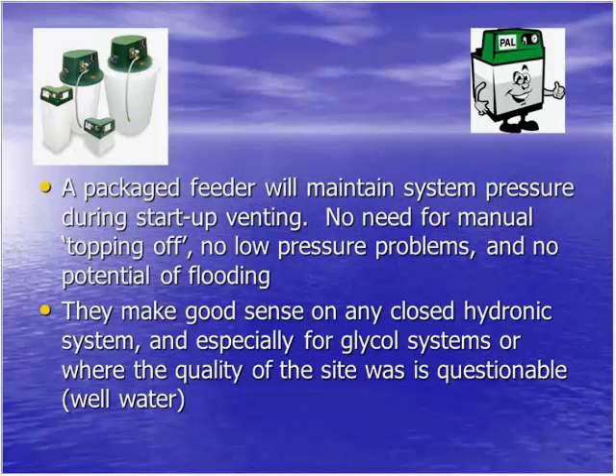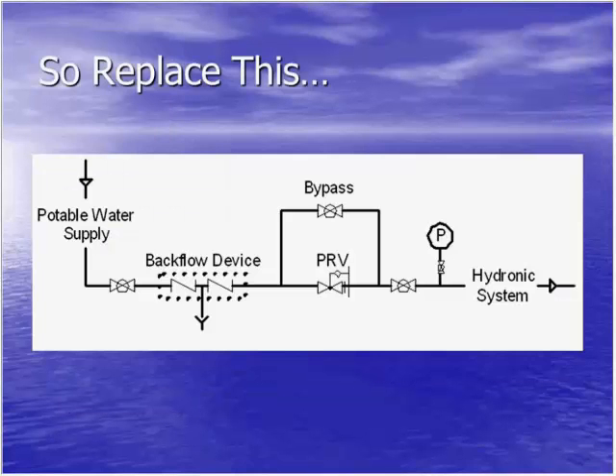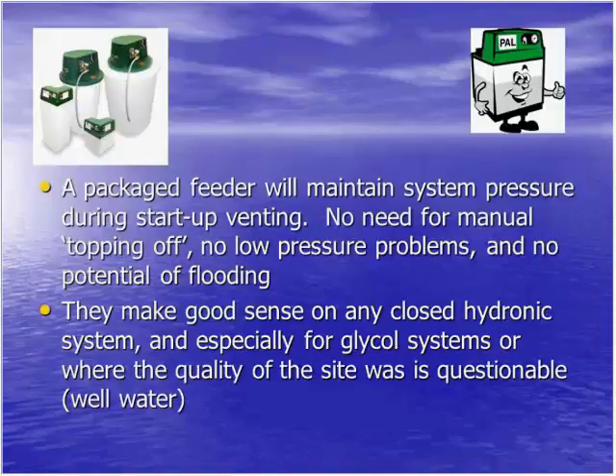So you can replace, sorry, Mark, go ahead. Quickly, I wanted to point something out, go back one slide. Okay. Back when I was still in the contracting business here in Denver with Advanced Hydronics, our insurance company approached us and asked us to use these systems. Their reasoning was that they needed some means of limiting their liability. When they discovered that we were putting 1 foot of pipe per square foot of living space, they had a hissy. And I said, you've got to do something to limit our liability or we're going to cease insuring you. So we approached them with this, and they said, that will work. And as you said, you can't lose any more than the volume that's within that tank other than what the system might be holding, but it's not thousands of gallons of water that would possibly do damage.